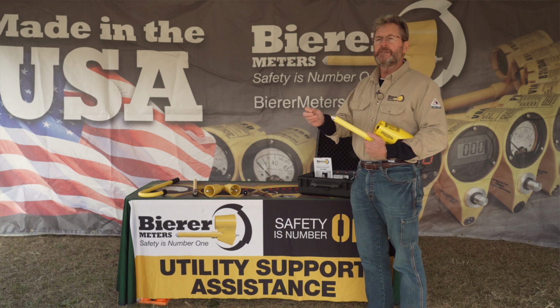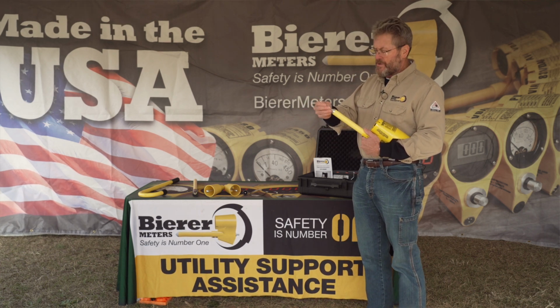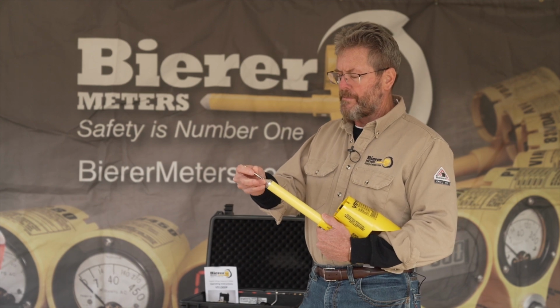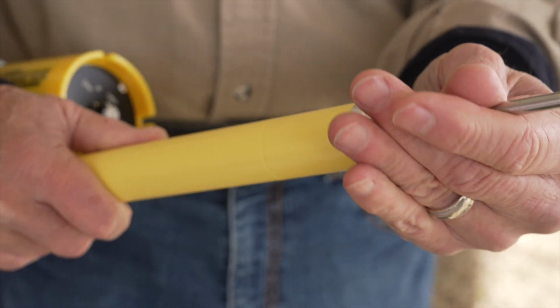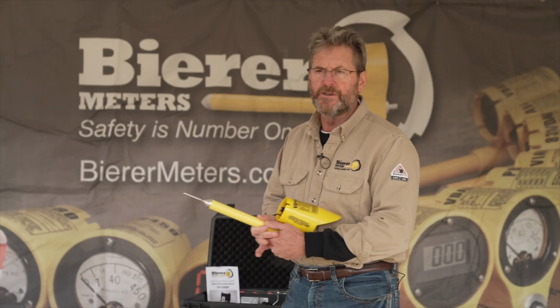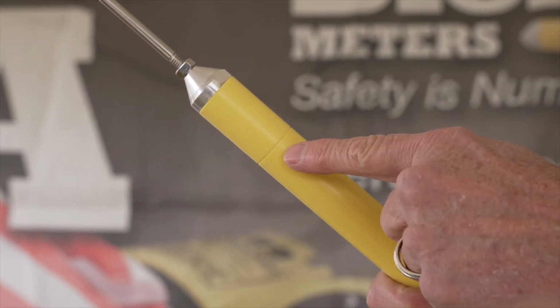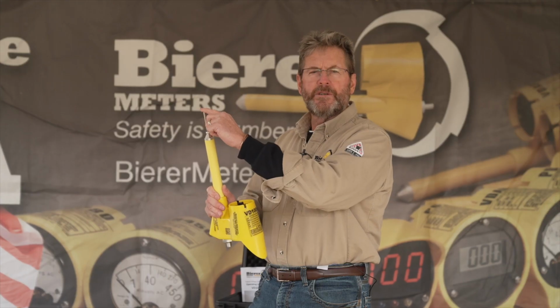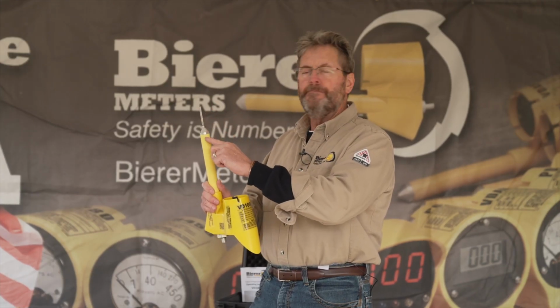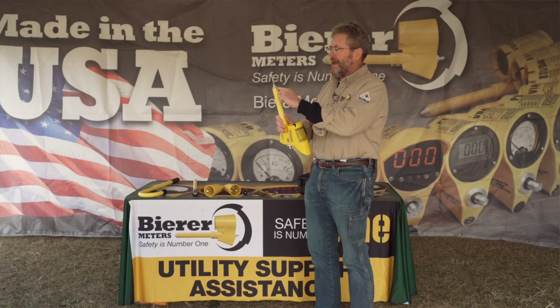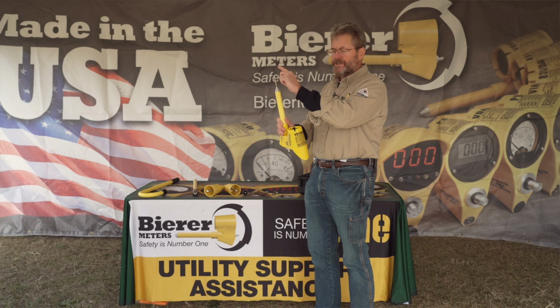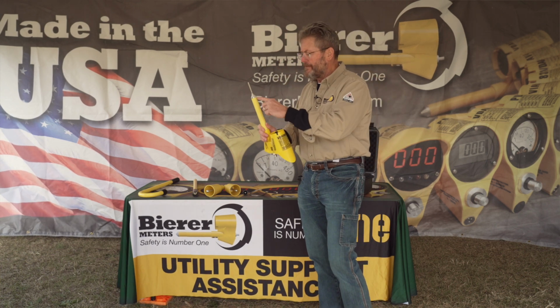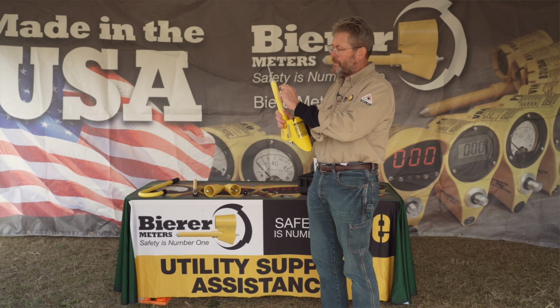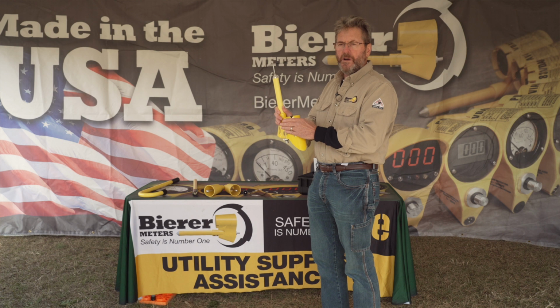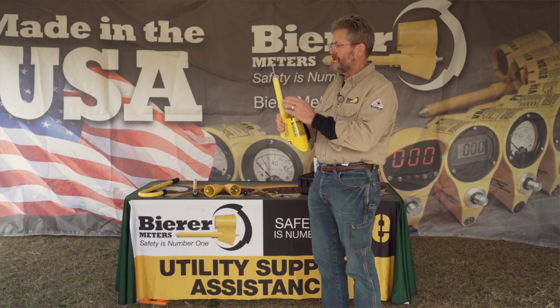The reason why you want to use these on your meter probe tip is you want to make sure that you have proper work methods and safety procedures. You're going to remember that in all the Bierer Meters products, there's a line limit right here. You want to verify that your meter probe accessory is in use because it helps mitigate bypassing that line limit. You have more length on the end of your meter probe. That extra length will help prevent bypassing that line limit, because there are resistors that protect the tool from primary power, from very high voltage. It's going to protect the tool.